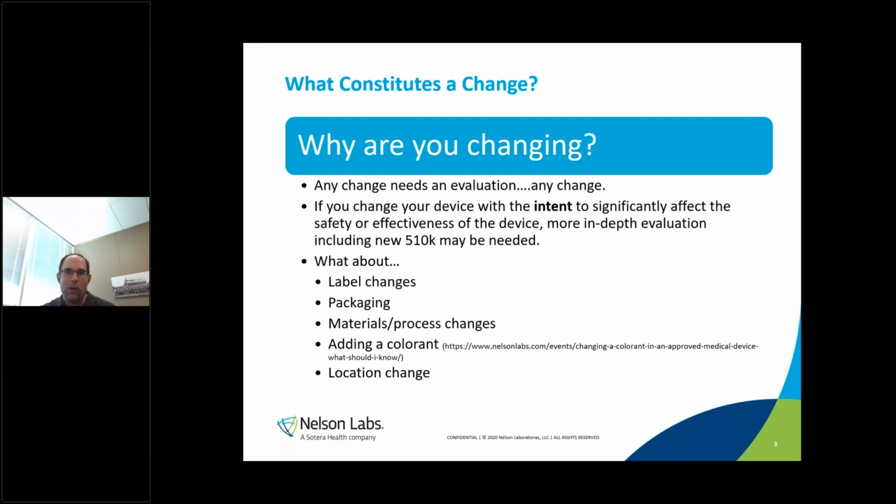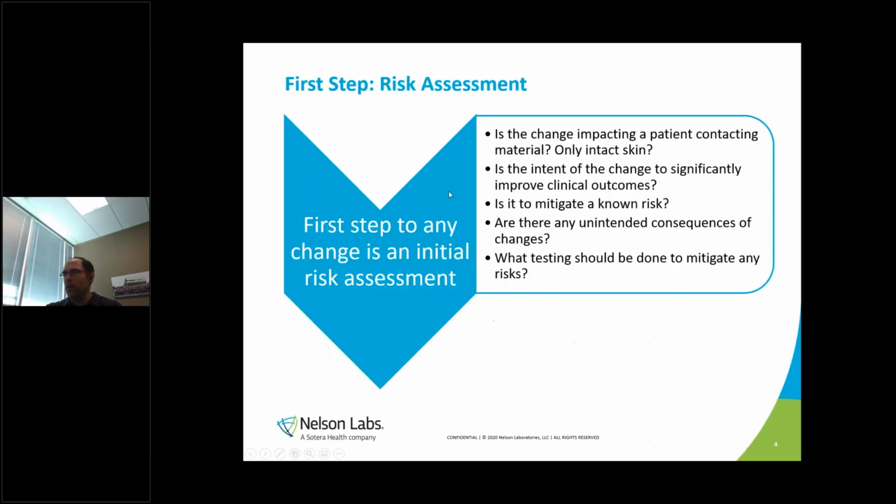But that just goes to show you that there are changes that could impact biocompatibility that could be surprising, right? So just things to think about when you're looking at changes in biocompatibility. So when you're looking at this, any change, like I said, should be assessed, not necessarily tested. I want to make sure everyone's aware of that, because I don't want you guys to think that I'm telling you you have to test on every single change. Every single change needs to be evaluated based on the risk to the patient.